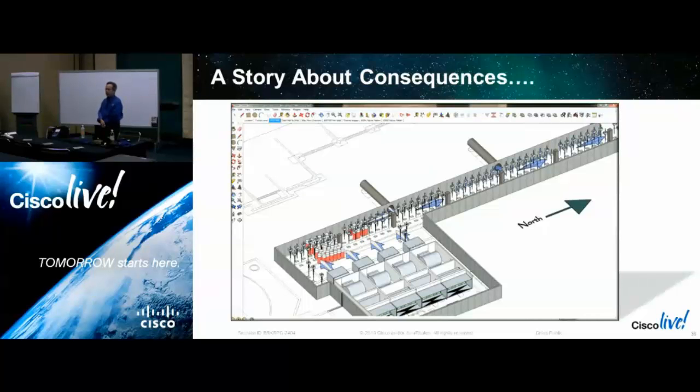And this was one of those situations where one fine, rainy July afternoon, 70 plus power supplies failed, from like noon to 4, thereabouts, on prime shift. They weren't all Cisco's, but a large part of them were, by virtue of where they were located in the data hall. It must have been a really exciting day in the data hall. They were reporting they heard a pop like a cap gun and saw a puff of smoke, and that's not what you want to see in your data hall.